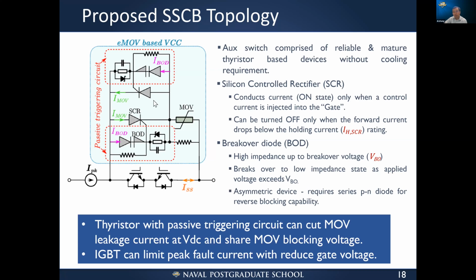The SCR, the main device, can be turned on if there's a gate current injected into the gate, and it will be turned off automatically if the fault current, the current flowing through the MOVs and SCRs, is below the holding current level. And we have the breakover diode. It's also a thyristor-based device. It behaves as high impedance, like an open circuit, when the voltage is low. When the voltage across it is high enough, it will turn on automatically and become low impedance. Because the SCRs and all the components are unidirectional, we have one group of these switches for each current direction, and we have this diode to make sure the current will not flow reversely. Also for the IGBT, we have already reduced the gate voltage, so you can see the fault current flowing through the system is already clamped.